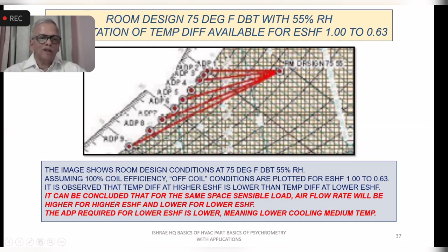And you can conclude that for the same space sensible load, the airflow rate will be higher for the higher ESHF and lower for lower ESHF. Let me clarify this. If you have X as the sensible heat to be removed, the sensible load, and you have 1 as the sensible heat factor, which means the line is horizontal, you get effectively the temperature difference from this point to this point. That is your delta T available for the heat pickup from the space, which means in your air quantity calculation, you will use this as the dehumidified rise. So in the calculations you will find that this is going in the denominator, which means for the same sensible load space, you will have to pump in a higher air quantity.